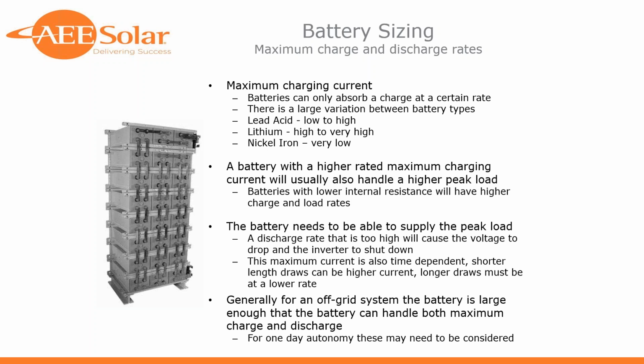There's different constructions of batteries. Some with thinner plates have much lower internal resistance and take considerably higher charge currents than other ones. There is some correlation between higher charge current and being a less deep cycle battery. Deep cycle batteries having thicker plates and being less able to absorb a high current charge. And of course, lithium batteries are generally known to take very high charge rates. Generally not an issue there.